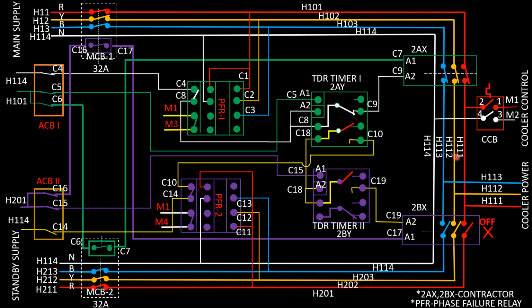H113, H112, H111. Now cooler power is on main supply. Now suppose main power supply through MCB1 fails or a single phasing occurs. This contact will break the circuit and no power returns through this circuit, and therefore the 2AX contactor breaks the circuit, and this contact will make to give access of neutral to the 2BX contactor through timer 2 after reset time. Now cooler power is on standby supply.